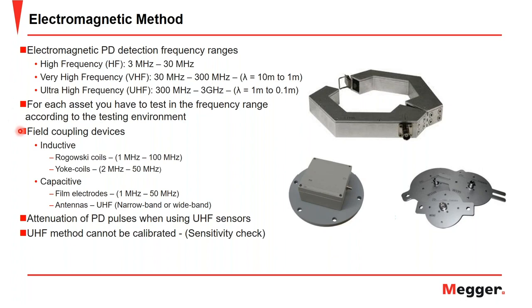When we talk about the field coupling devices for electromagnetic methods, there are two different types, inductive and capacitive. The inductive type can include Rogowski coils with measurement frequencies ranging from 1 megahertz to 100 megahertz, or yoke coils ranging from 2 megahertz to 50 megahertz. An example of an inductive field coupling device is this CT seen here. There are capacitive field coupling devices, such as film electrodes, that range between 1 megahertz and 50 megahertz, as well as antennas in the UHF range that cover both narrowband and wideband measurements, with narrowband being about 5 megahertz and wideband being up to about 2 gigahertz. These are primarily seen on GIS.